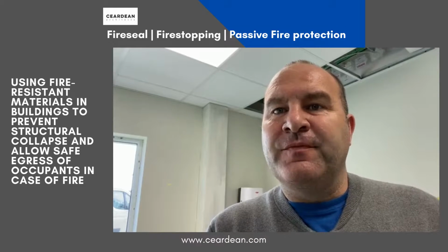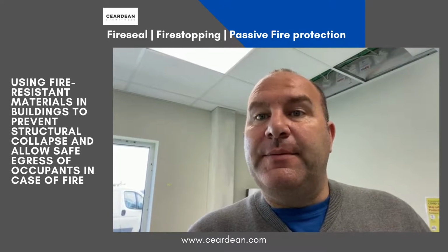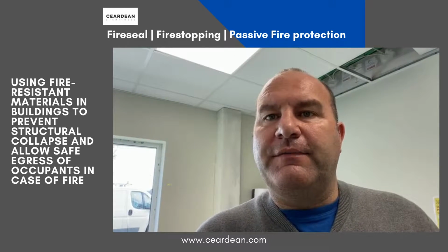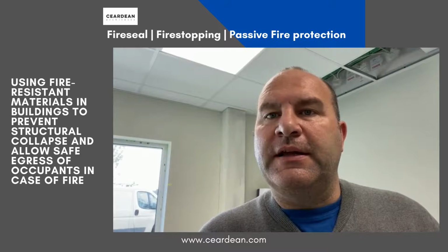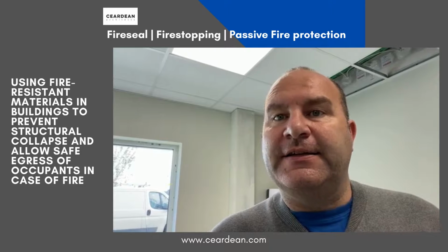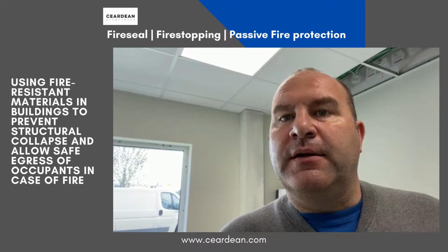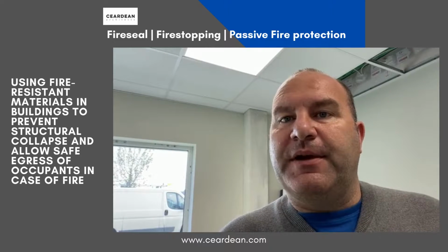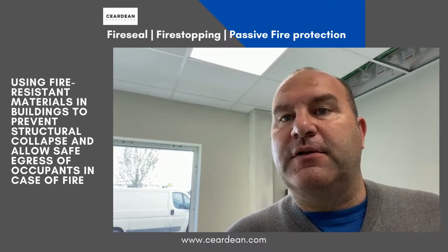Derek Treneman. I'm here at a project we're working on, and I'm just going to show you a little bit of fireproofing work that we're doing. It's very important that all the particular firewalls are fire stopped correctly and tagged. I'm just going to show you a few instances where obvious fire stopping was sealed, but also some areas where things occurred by accident and had to be sealed afterwards.